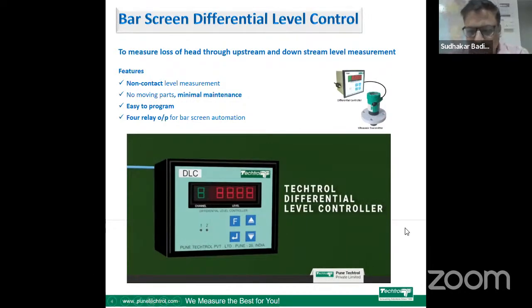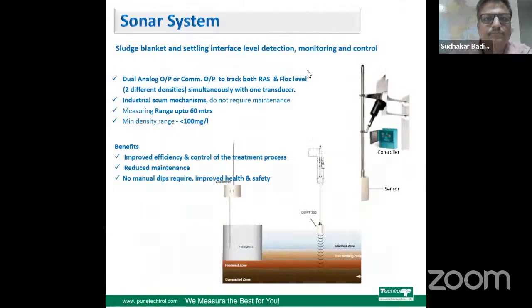So this is how this system works. This is a sonar system, mostly used in the clarifiers. It is used to measure underwater sludge detection.